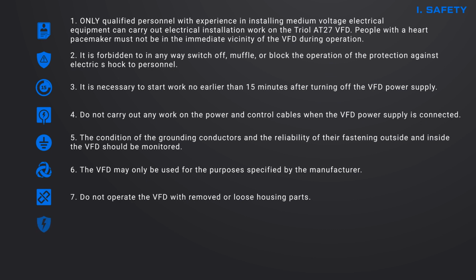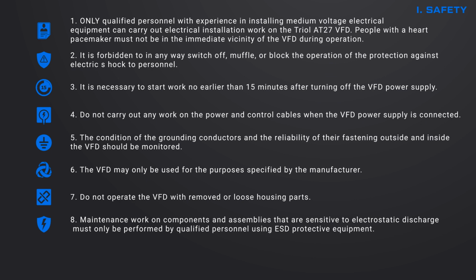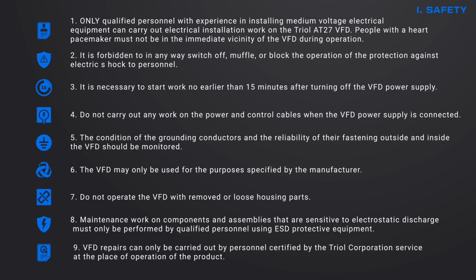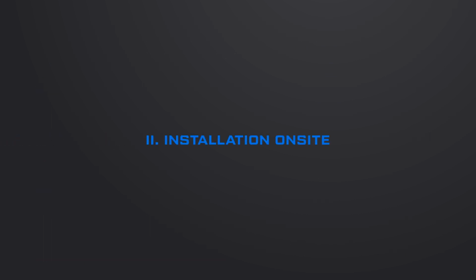equipment damage. Printed circuit boards contain static-sensitive components. Always wear an ESD wrist strap when handling printed circuit boards. Do not touch the boards unnecessarily. Maintenance work on the VFD on components and assemblies that are sensitive to electrostatic discharge must only be performed by qualified personnel using ESD protective equipment who are experienced in servicing converter technology. Failure to handle electrostatic sensitive components safely can damage the VFD. VFD repairs can only be carried out by personnel certified by the Triol Corporation Service at the place of operation of the product. Installation on site.